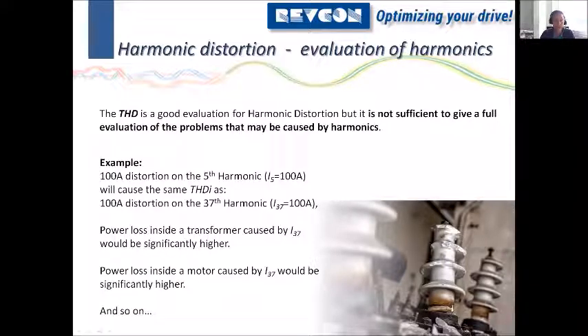And first of all, that's a waste of energy, because all these harmonics are energy. But more of a problem is that your transformer may overheat and see problems. So even though it's not loaded significantly, all the energy from this signal will not be transmitted, so you will heat it up quite quickly. That's the main reason why transformers heat up from harmonics. They are not able to transmit all of the harmonics.